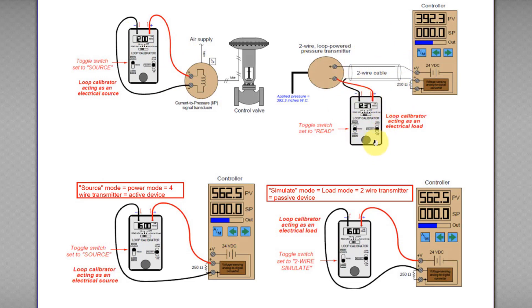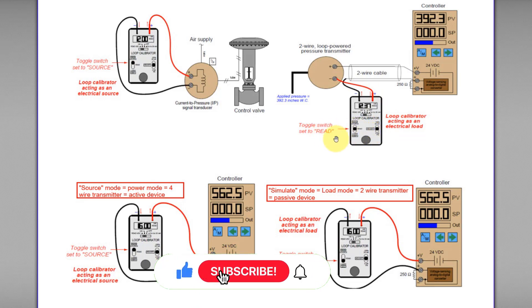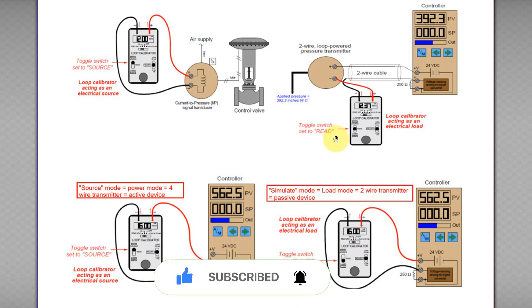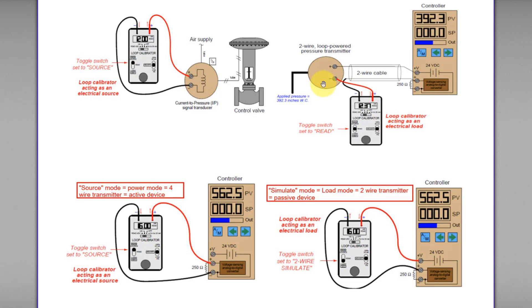This signal calibrator switch is set to read mode. Read mode is actually a measurement mode, which is no different from a normal multimeter measurement mode — the same mode we use daily to measure current and voltage. Since we are measuring the 4 to 20 milliamp current in this circuit, we connect this loop calibrator in series with the controller and the transmitter. The loop calibrator will act as an electrical load, since it is no different from a normal multimeter.